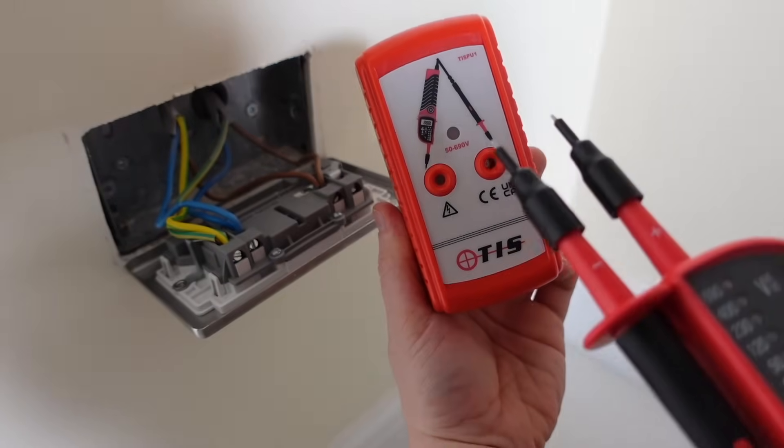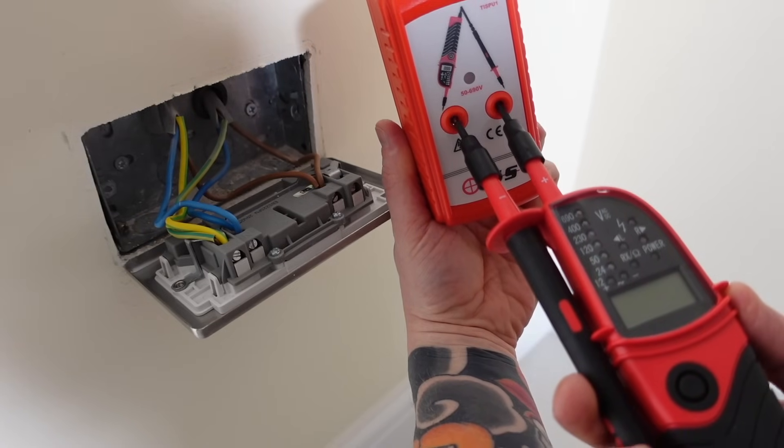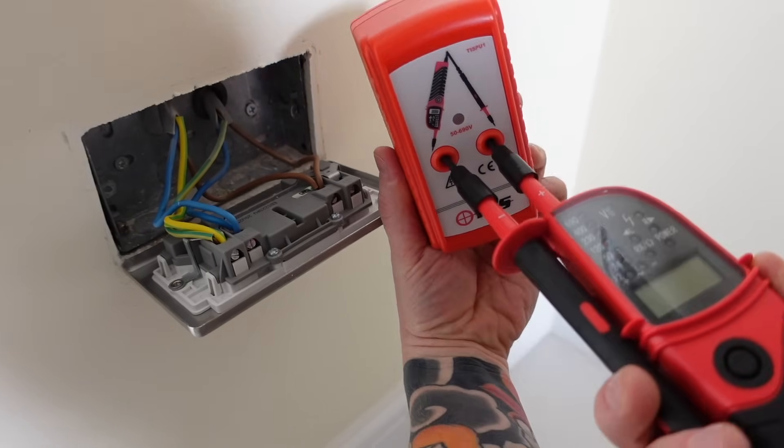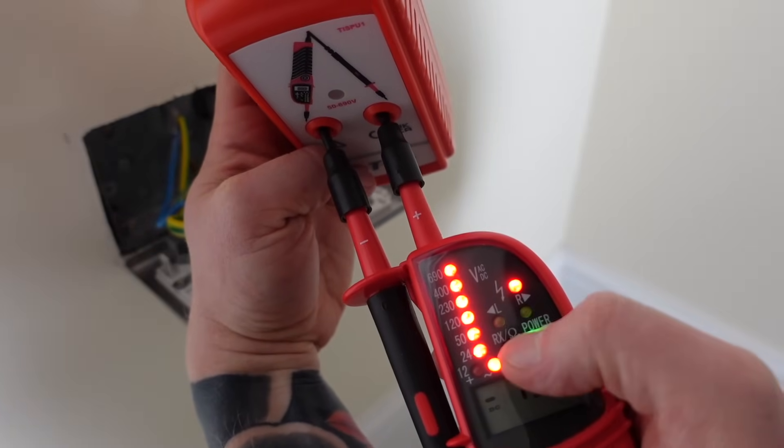So our proving unit here is a simple device that'll tell us if our voltage tester is working. We just insert the probes into the proving unit and you can see there we're getting a voltage reading on our volt tester.